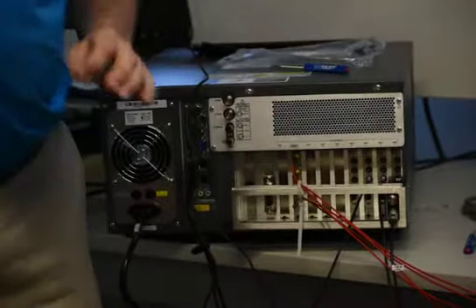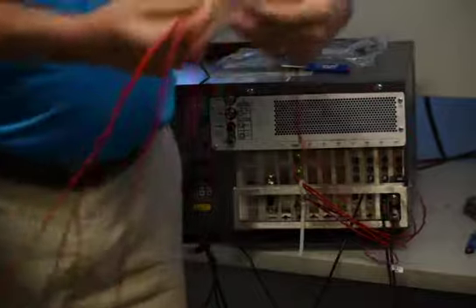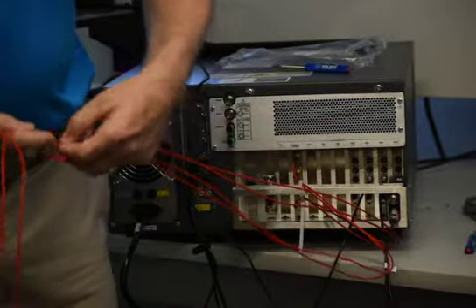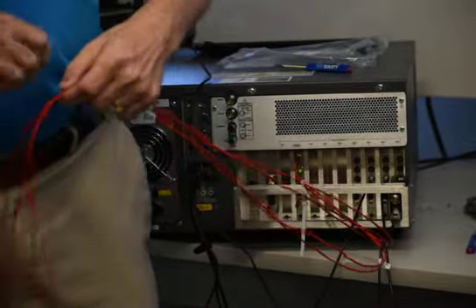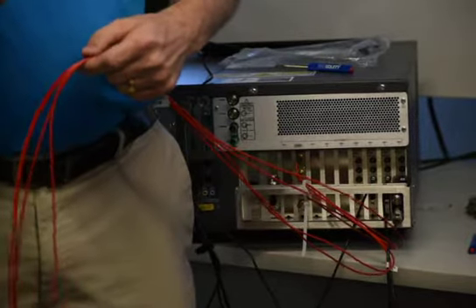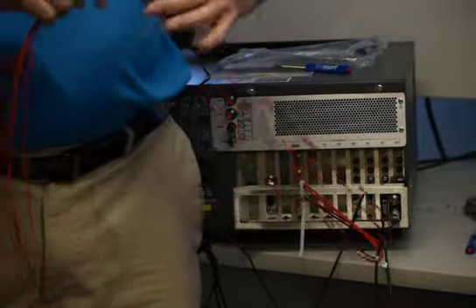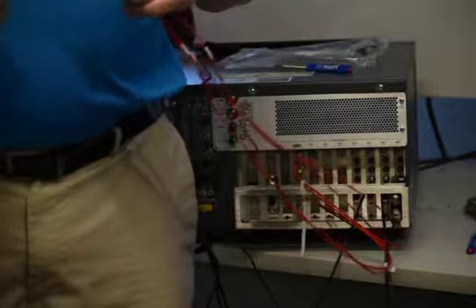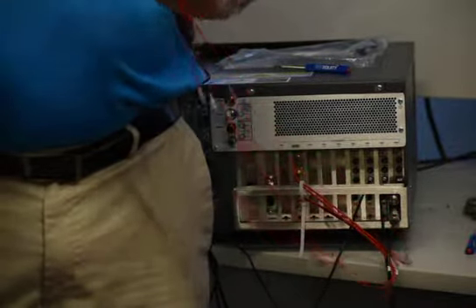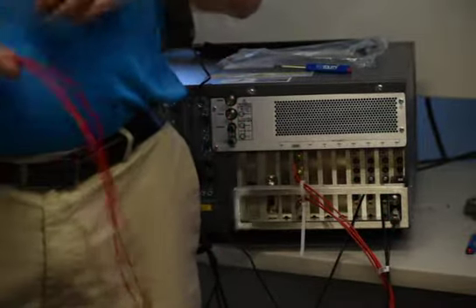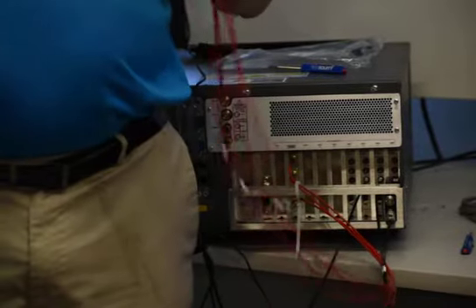And another thing I noticed is it's the cables. You want to take very good care of these cables. And I noticed there was some kinks in one of these cables. You want to be very careful with these, because a kink is another opportunity for a reflection, right? Any kind of damage to these cables will affect your measurements. These are, like I said, sensitive measurements, so they require you take care of this stuff, right?